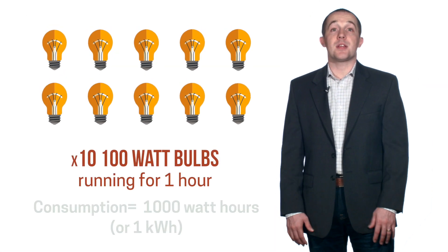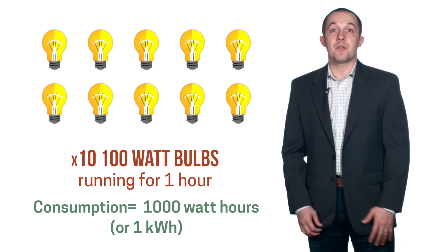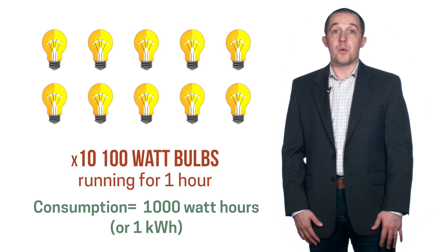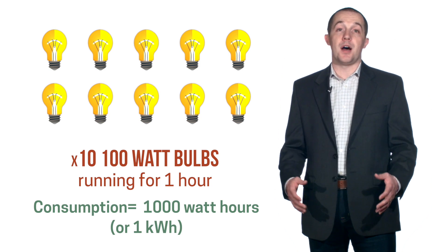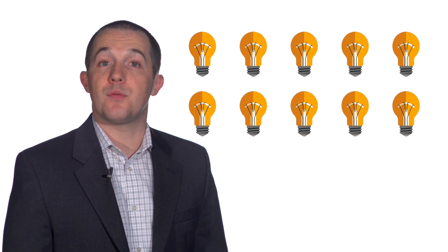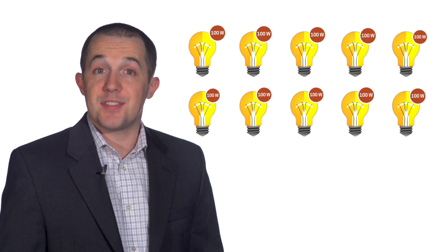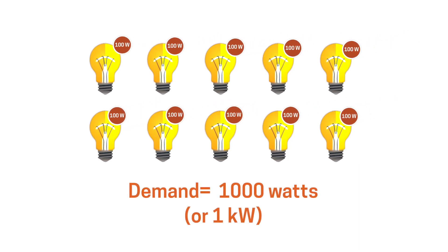Now let's imagine a bank of 10 100-watt light bulbs that we run continuously for 1 hour. That's 1,000 watts consumed for an hour, which means our consumption is 1,000 watt hours or 1 kilowatt hour. Each bulb, however, has an individual demand of 100 watts or 0.1 kilowatts, but now we have 10 bulbs, which combined demand 10 times the energy from the utility than a single bulb. 10 100-watt bulbs running for 1 hour would mean our demand in this case would be 1,000 watts or 1 kilowatt. To meet our demand, the utility must have 1 kilowatt ready at all times in case all 10 bulbs are turned on.